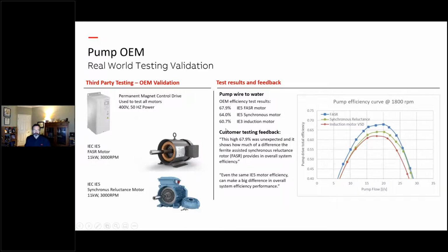They actually picked up, and this is system efficiency, so this includes the pump losses, 7.2% efficiency over an induction motor, and surprisingly 3.9% pump system efficiency over another IE5 design. And that's just really because it's holding that partial load efficiency at a higher level. So depending on the pump design curve and where it's operating, you can see significant gains over different other technologies.